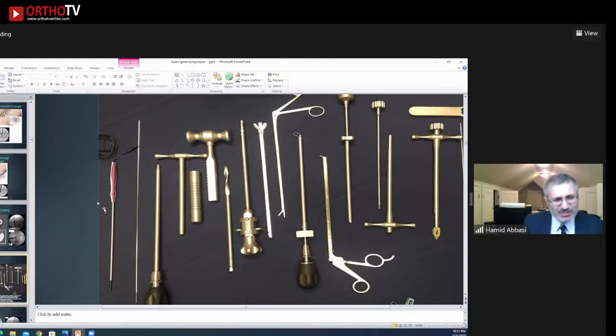This is a specialized neuromonitoring probe. Practically, you put electrodes in the legs and in the abdominal region if you're working on the thoracolumbar region. You put a 3 milliamp stimulation signal on it, and you capture the data from the muscle groups to see if you're too close to the nerve root or not. It is insulated. The metal sleeve over the probe is not part of the probe. The probe is insulated with Teflon, and the tip of it is bare, meaning that is the only area that can give the stimulation. We approach at 3 milliamp, and once we get too close to a nerve, we just have to reposition.